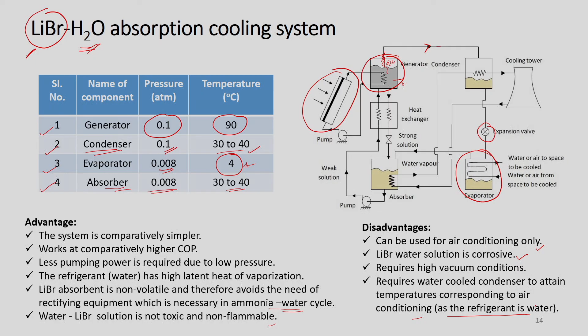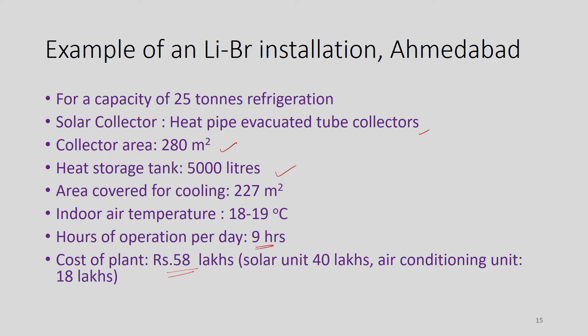Let us take an example which has already been installed in Ahmedabad. For a capacity of 25 tonnage refrigeration, the amount of solar collector required and the investment required can be seen here. The solar collector type is heat pipe evacuated tube collectors, and a collector area of about 280 meter square is required. Heat storage tank capacity is about 5000 liters, and the area covered for cooling is about 227 meter square. Indoor air temperature is about 18 to 19 degrees C, and hours of operation per day is 9 hours. The cost of the plant is 58 lakhs, which includes the solar unit at 40 lakhs and the air conditioning unit at 18 lakhs. It is a costly system.